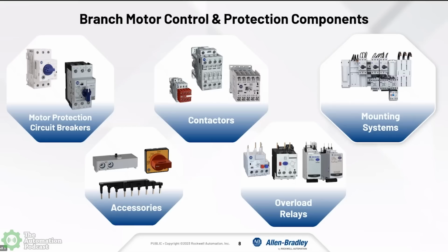We do have some tools that allow customers to easily select. One tool I'll highlight initially is our global SCCR tool, the global short circuit current rating tool. You can see how these products have been rated together for various applications. Additionally, you can use some of these products in conjunction with other Rockwell products. For example, the motor protection circuit breakers can be used in front of our VFDs, some of our smaller VFDs, as branch circuit protection. We've got updates in that tool that allow a customer to see what that short circuit current rating is with this 140 MT and their PowerFlex 520 or PowerFlex 750 series drive.